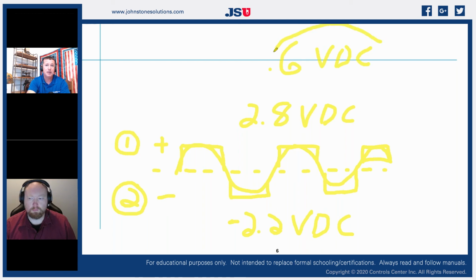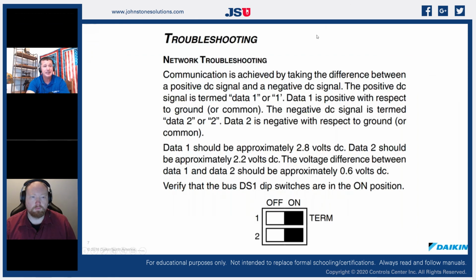So if I take my meter and I check between number 1 and number 2, I'm actually going to have a 0.6 volts DC bias. The difference, the bias, is going to be the difference between those. And that's that bandwidth that we're going to talk on. That's where all of our signal is going on, in that little bandwidth in between those voltages. So we have to have a bandwidth to be able to get all of our signals through there, just like we have to have a bandwidth for any type of other communications. So it's important to understand that bias. If we look in the installation manual, it's going to be very specific on that bias. It's going to tell us that we need, on number 1, a positive signal with reference to ground of about 2.8 volts and a negative signal of around 2.2, a bias of about 0.6 volts difference.